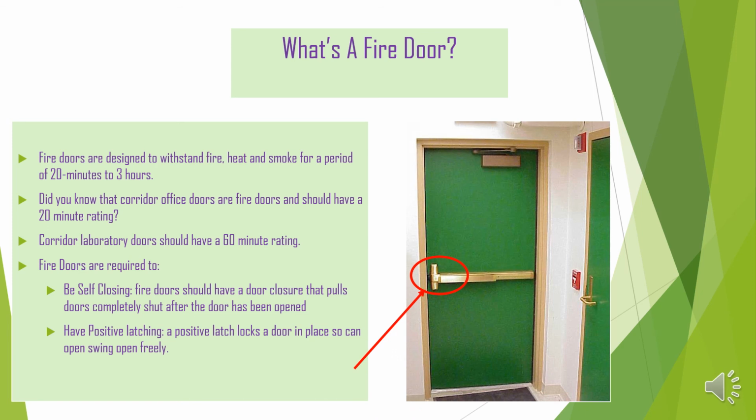You can open it from inside, just push it without any keys, push it and go out. It will be locked automatically, it will swing and close. It will withstand the fire for 20 minutes up to 3 hours in some doors, so you can evacuate your people, you can execute your plan without being afraid that the fire will cross that door.